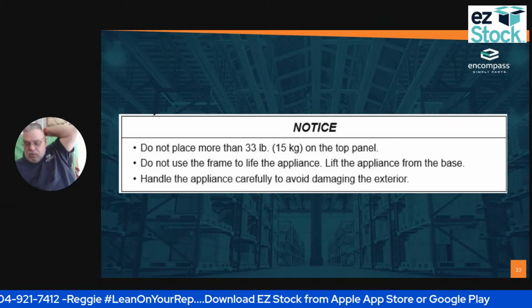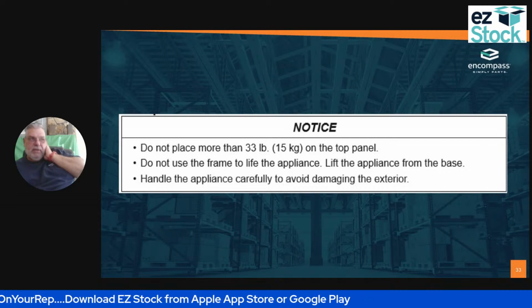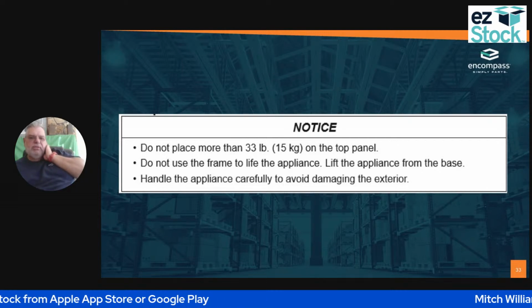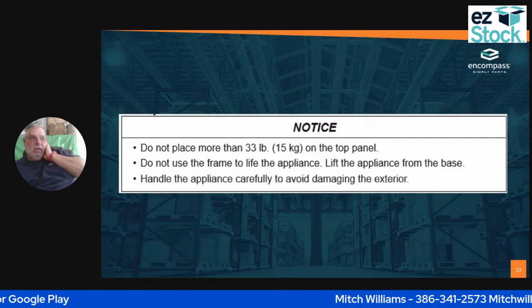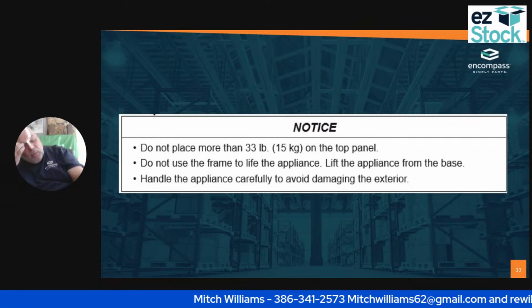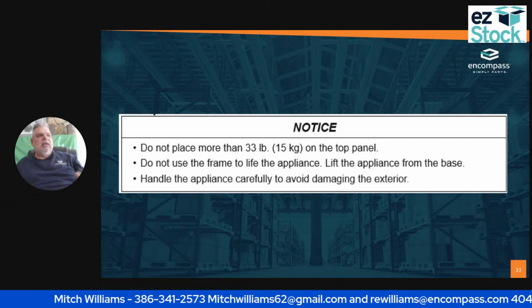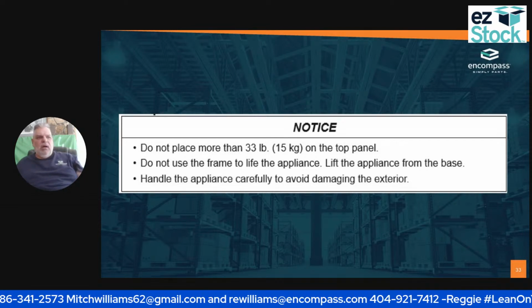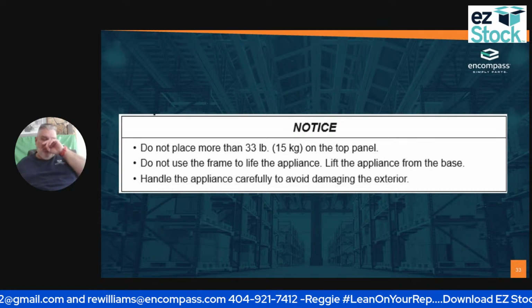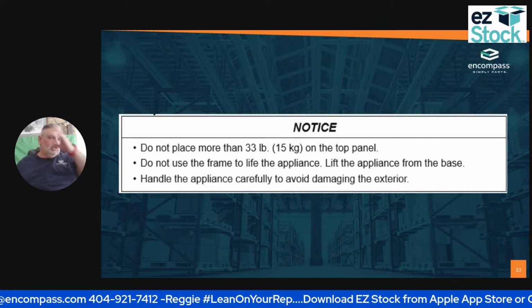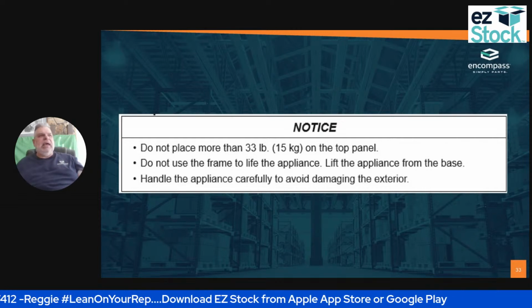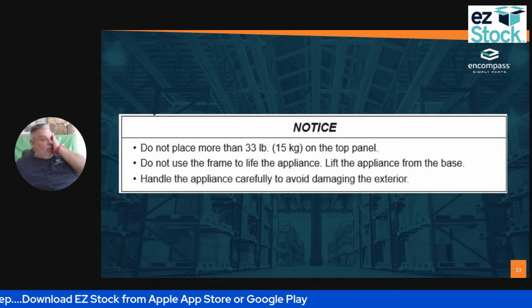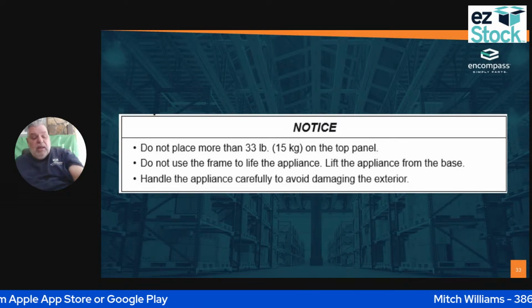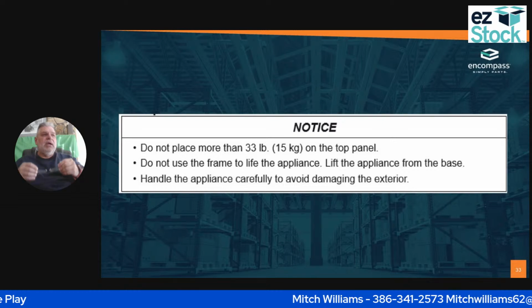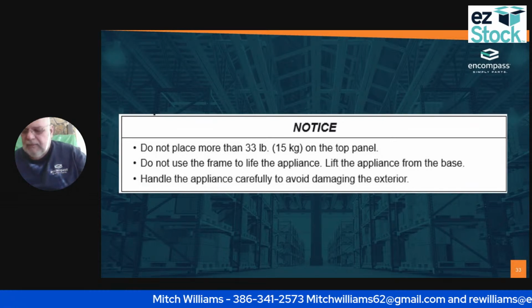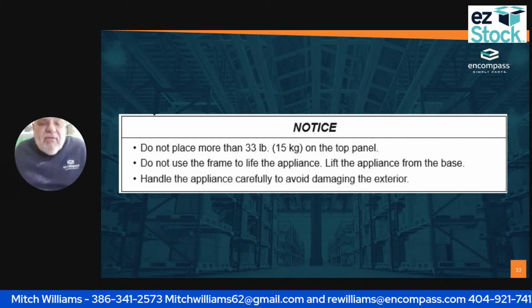That's for the Manitowoc. The Manitowoc, I think, is 45 pounds, but if you keep it under 33 pounds, you know that you're good. And the problem is, whenever we have an ice maker, you can't lose the flow of air, because if I do, I slow my ice production down. So if I have stuff piled on top of this and it's in a cabinet, I've got to make sure that I have the proper amount of airflow that comes through. And one of the ways you're going to tell is if it's really hot coming out, you probably don't have the right amount of airflow going to it.